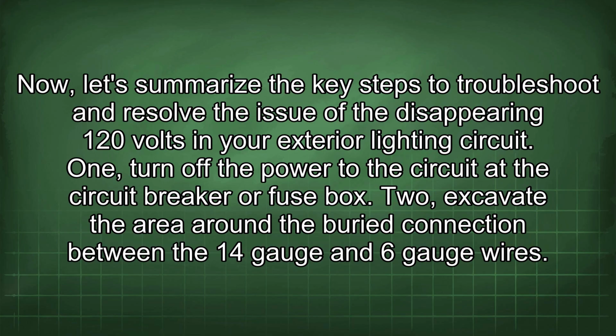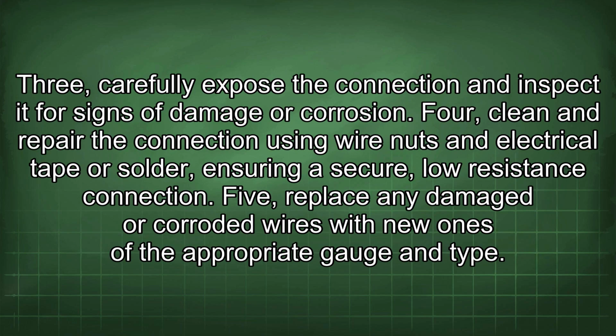Now, let's summarize the key steps to troubleshoot and resolve the issue of the disappearing 120 volts in your exterior lighting circuit. 1. Turn off the power to the circuit at the circuit breaker or fuse box. 2. Excavate the area around the buried connection between the 14 gauge and 6 gauge wires. 3. Carefully expose the connection and inspect it for signs of damage or corrosion. 4. Clean and repair the connection using wire nuts and electrical tape or solder, ensuring a secure, low-resistance connection. 5. Replace any damaged or corroded wires with new ones of the appropriate gauge and type.